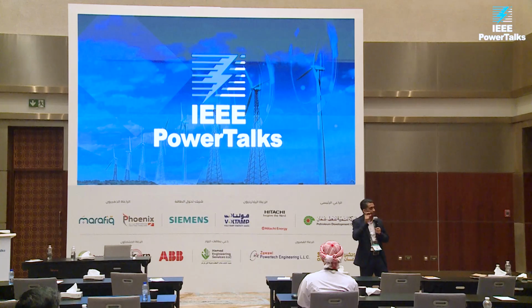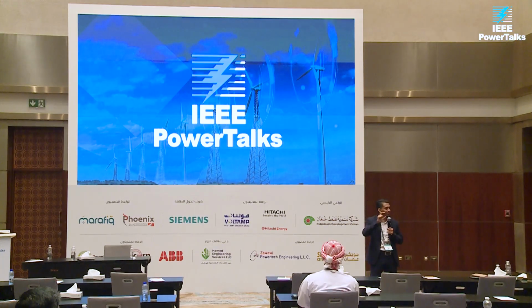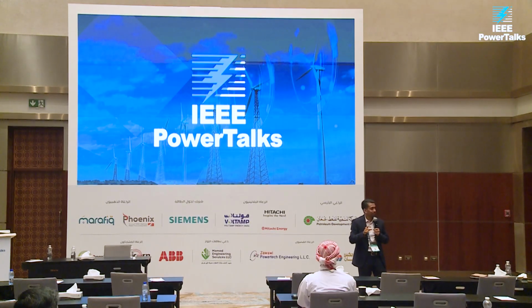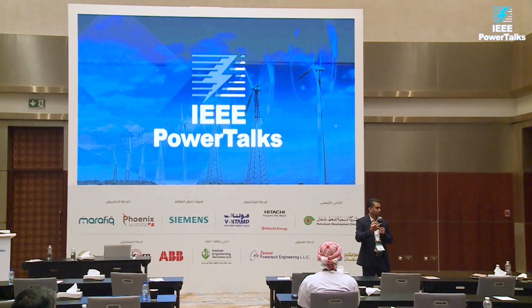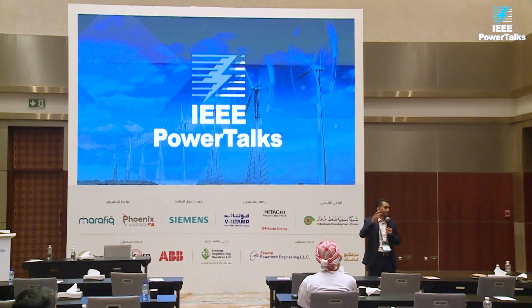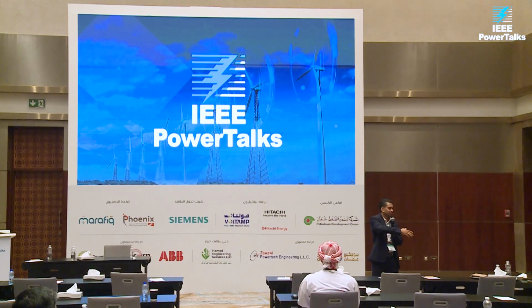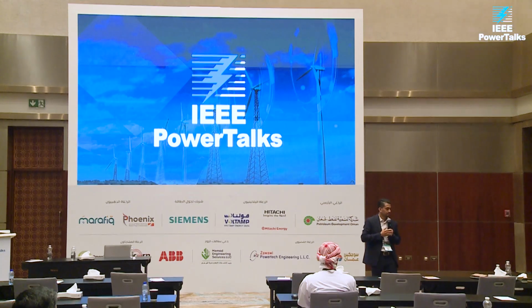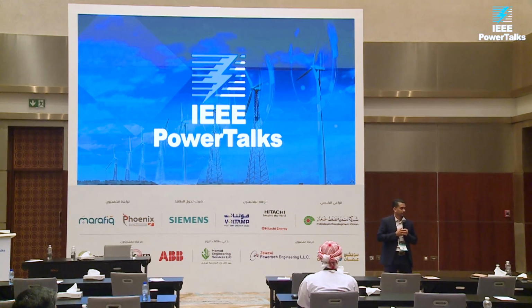So now you have, from these sensors, information that also tells you whether the fault is temporary or permanent. If it is permanent, yes, you have to send somebody to that particular location where the fault is. But if it is temporary, you can tell the SCADA that yes, it's a temporary fault, you can immediately close the breaker. Okay, for this it can be in OHL, right? Yeah, in OHL. Similarly for underground cable network.